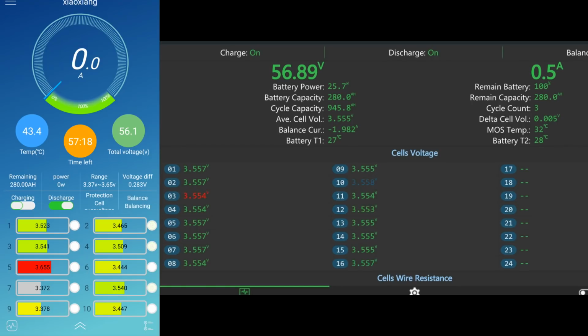Which still gets balanced, and we are now at 5 millivolt deviation with this battery. Because we have set 3.6 volts as the recovery voltage, the QUCC BMS will wait until we reach this voltage with cell number 5, which is the highest. Then it will turn on the relay again and connect both battery banks together.